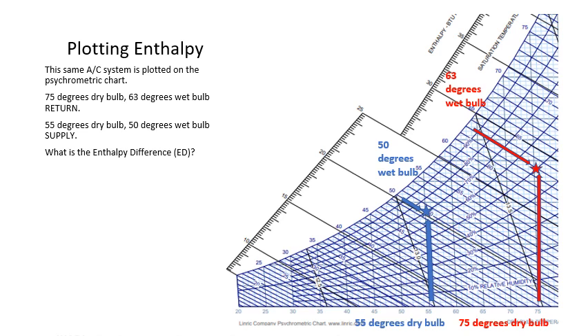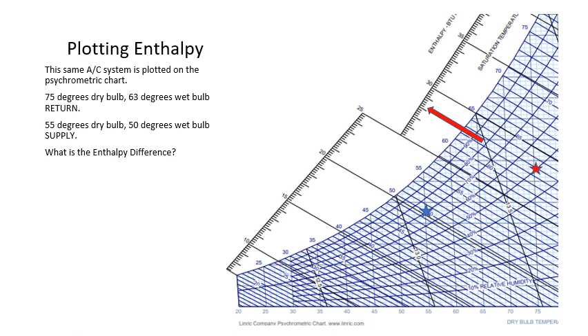Now let's try to plot our enthalpy. The enthalpy is just an extension of the wet bulb line, which runs diagonal on our chart. If we plot this out, we arrive at 28.1 BTUs per pound of return enthalpy. On our supply side, we just extend that wet bulb line up diagonally to the upper left, and we arrive at 20.3 BTUs per pound of supply enthalpy. So, how much enthalpy did this system remove? The difference between these two lines is 7.8 BTUs per pound.